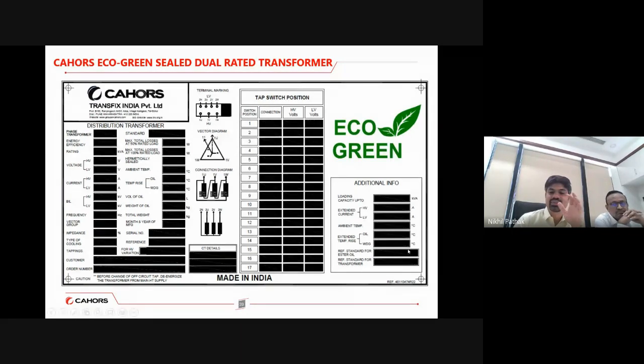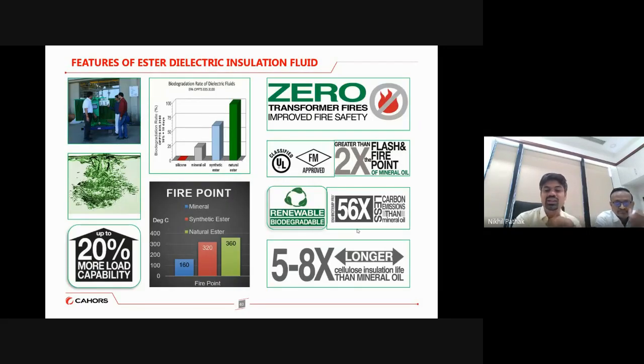So here what is happening, even if the transformer is overloaded, because the natural ester oil has a fire point above 300 degree, which is 360 degree. That is the reason the transformer oil can even deal with high temperature situations also. That is the reason, even if the overloading happens, the oil and the transformer will not come into a panic situation, and it will still be able to deliver the power without any compromise on the life expectancy, or without deteriorating the insulation strength of the transformer. So now these are the briefing with the features of natural ester oil. So it offers 20% more load capability.